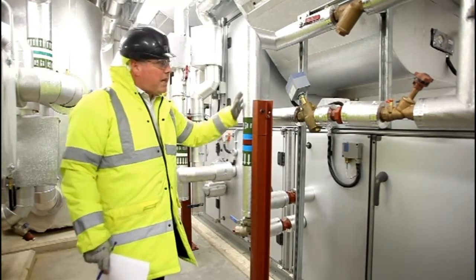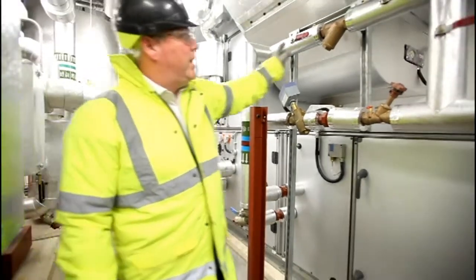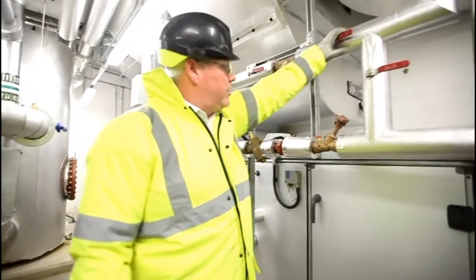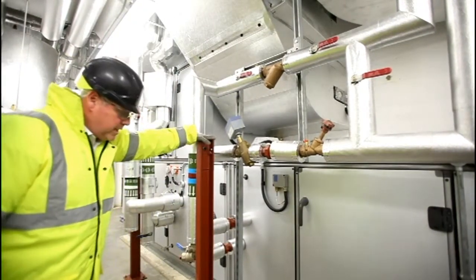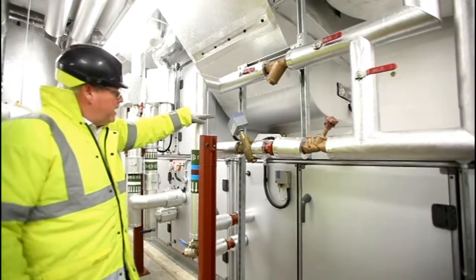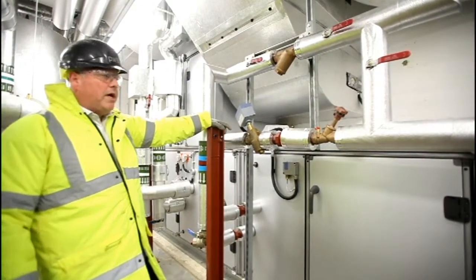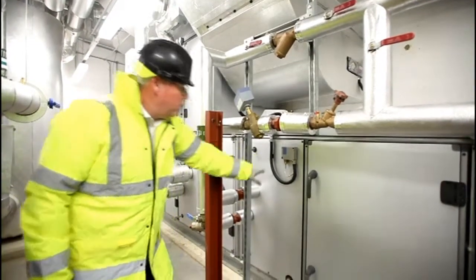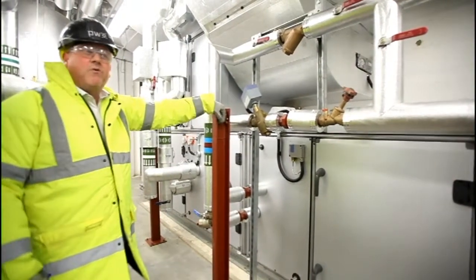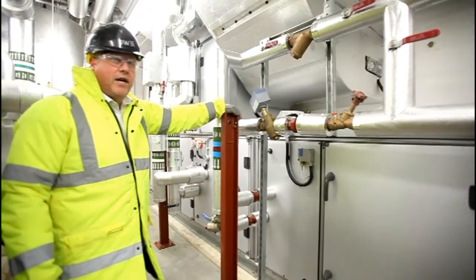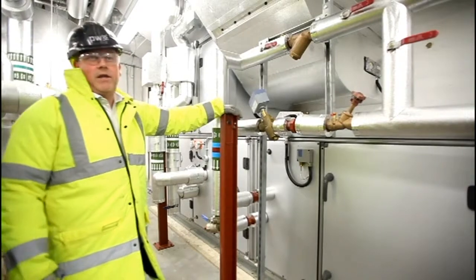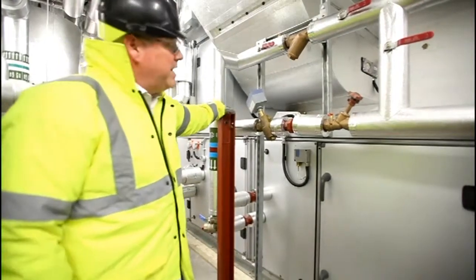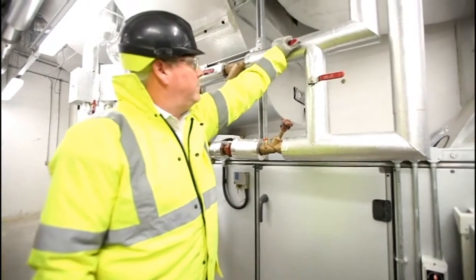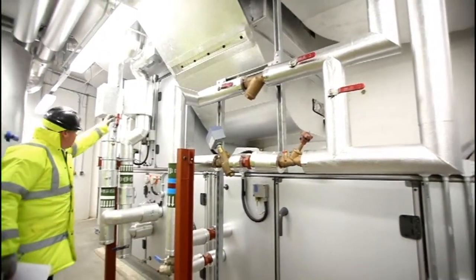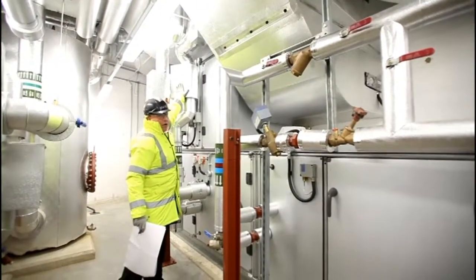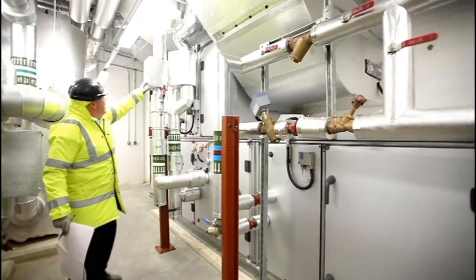Again, main isolations for the units are clearly shown and will be identified. Should there ever be an issue, for instance, each plant room has leak detection. Normally, if there is an issue with the unit, it'll be the heating coil, which essentially is a large radiator. They look very like the radiators that we get in our cars, obviously on a larger scale. Should there be water detected via the alarm or on physical checks, these can be isolated here and here. Same in this one, here and here. On the cooling, a lot of the valves are behind what we call valve boxes.